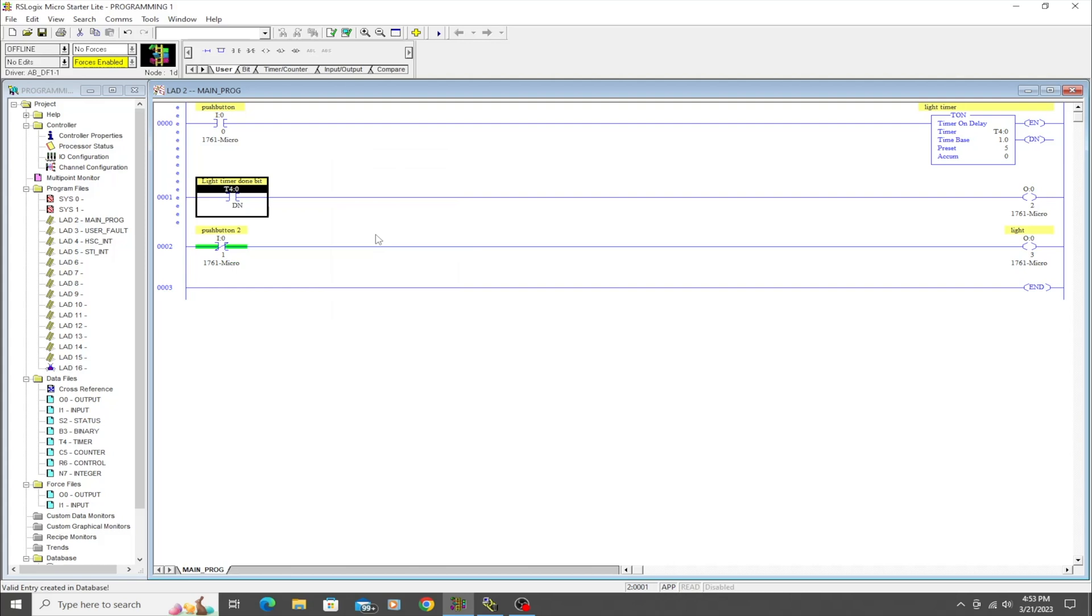With the way I just addressed this over here, when timer 4 is done, it's going to make this examine-if-closed instruction go high, which is going to pass logic. So if I hit enter, now it wants a new description because it is now a different instruction. It's the same instruction type, but it is now associated with a different bit. Before it was associated with a direct input on the PLC, but now it's associated with this timer. So now it needs a different description.